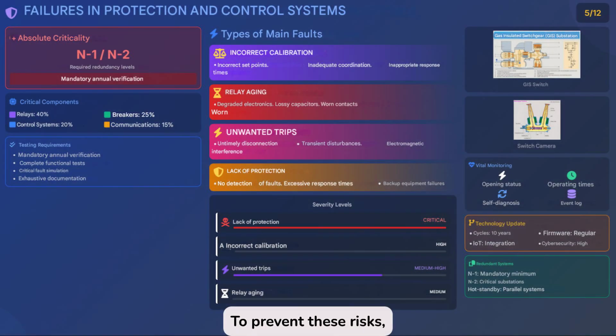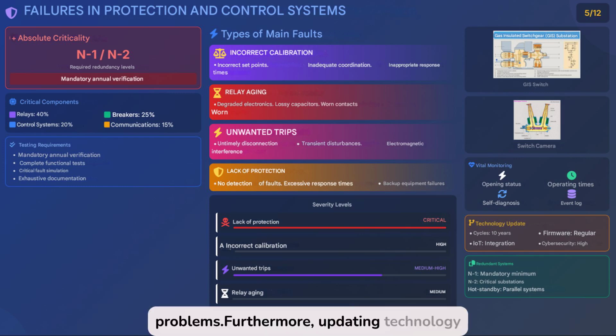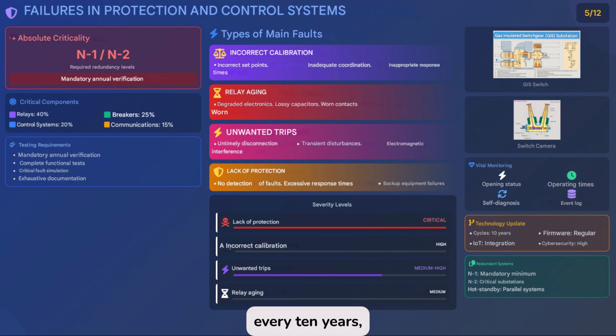To prevent these risks, it is essential to conduct comprehensive functional testing, perform fault simulations, and maintain clear documentation. Continuous monitoring of equipment status, operating times, and self-diagnostics helps anticipate problems. Furthermore, updating technology every 10 years, integrating IoT, and strengthening cybersecurity reduces exposure to threats. And of course, backup systems must be operational.